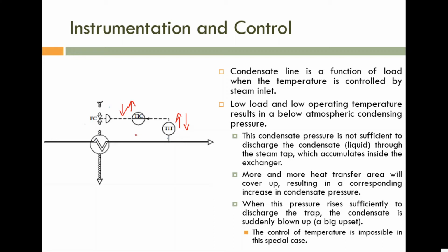So now, what are the disadvantages? The disadvantages discussed for the liquid to liquid heat exchanger are all applicable. Means we can use this instrumentation if the process is not regularly affected by disturbance and the time lag is not large. If the process has high time lag and high load effect, then we can't use this instrumentation. We have to use a bypass line. Okay, so the same instrumentation we can use here.